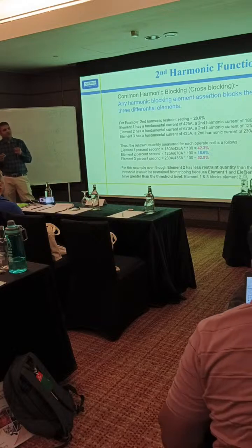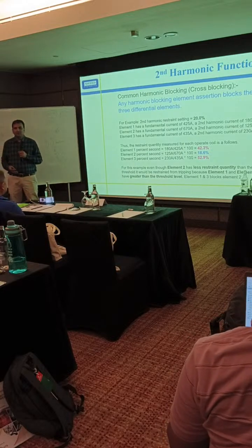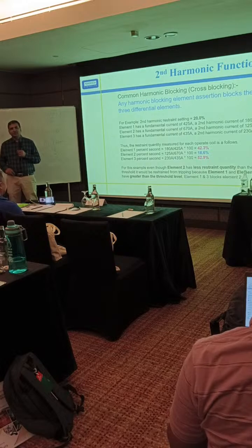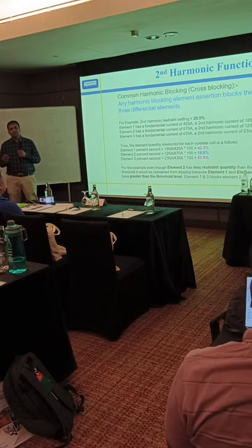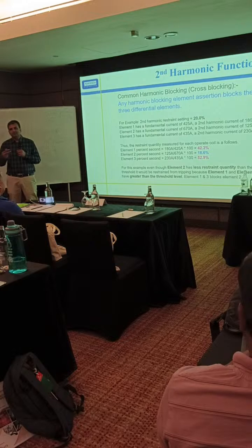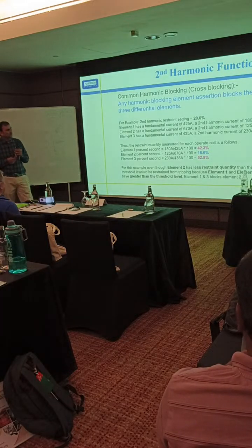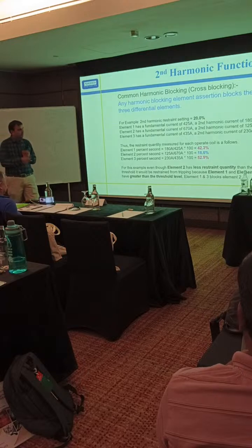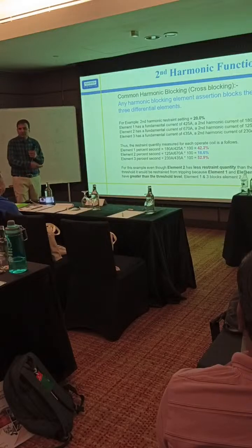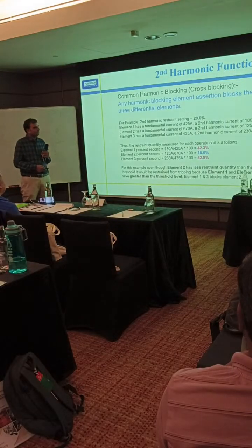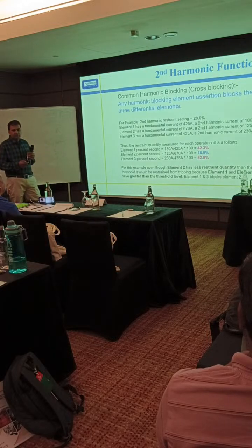They told that the relay has not maloperated. It is working well. And for 4 months we are following, but still have not received the answer. So that is why it is quite confusing. We should enable cross blocking or not. But you understand the concept. Okay? If any question, you can ask.